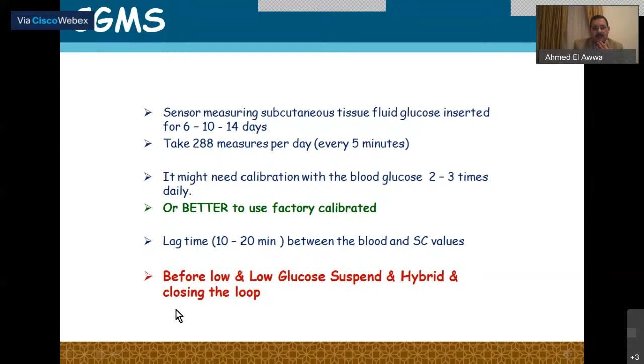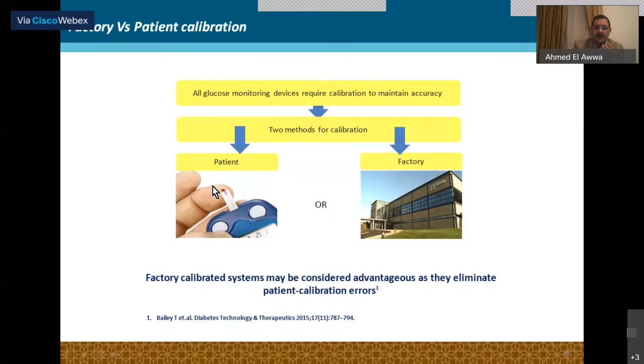So you don't need to make calibration. It's calibrated in the factory, and the sensor will not ask for any glucose calibration. So it's very convenient for patients to have a factory calibrated sensor. Of course, a lag time is expected between the interstitial fluid and the blood, which is well understood. The accuracy of the sensor is measured as a percentage of accurate readings against the blood reading, and the validation of the sensor is based on that. As we said, it's now integrated with the pumps. So factory calibration is very important to overcome technical issues or false data entry by the patient that would affect the accuracy of the sensor.